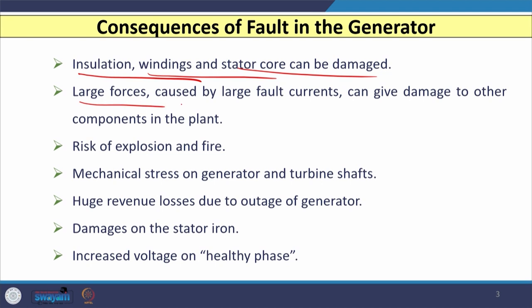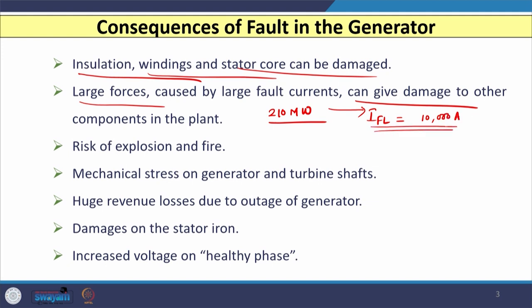Large forces may develop because of the large magnitude of fault current, which can also damage other components of the plant. For a 210 megawatt generator, the full load current that the winding can carry is very close to 10,000 amperes. If a fault occurs, 6 to 10 times this current flows through the winding, producing large forces that may damage several other components. There is also a chance of explosion and fire because of the large magnitude of fault current.